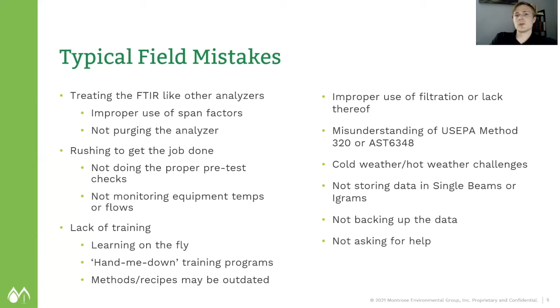We have the test data. We kind of understand what to look for on the sampling side, but how does this impact your data? Once more, the loss of temperature and a little bit of a dirty instrument is not going to really impact your NOx, your CO too much. It will at a certain point, but for the most part, you'll be okay. But this is going to greatly impact your low-level detection analytes, especially if you're using a star boost or a new upgraded FTIR with different path lengths. These advanced instrumentation pieces will take the greatest hit.